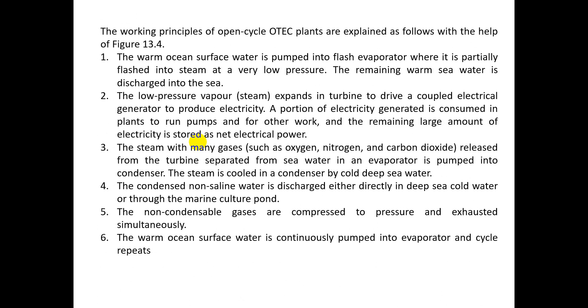The working principle proceeds as follows: initially, warm sea water is pumped into the flash evaporator where it is partially flashed into steam at very low pressure, with the remaining water discharged back to the sea. Second, this low pressure steam expands and hits the turbine, generating electricity. A portion of the generated electricity is consumed within the plant to run the pumps and other equipment. The steam may also carry non-condensable gases such as oxygen, nitrogen, or carbon dioxide, which are separated from the turbine.